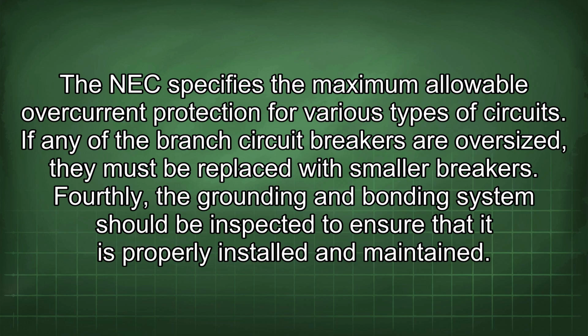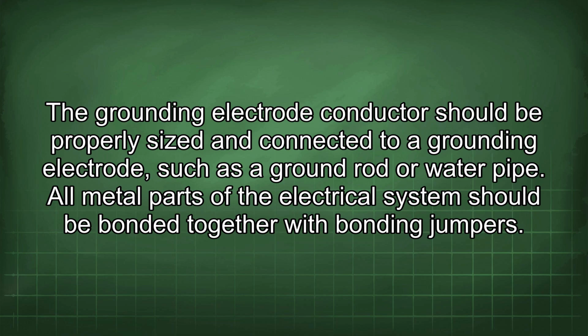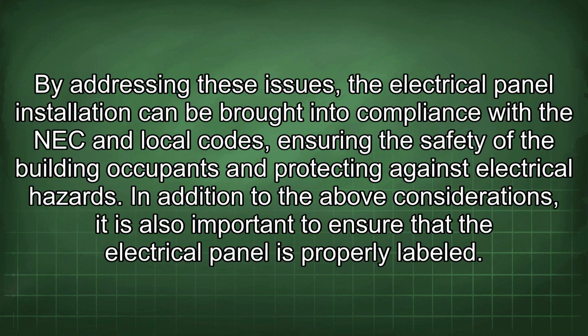Fourthly, the grounding and bonding system should be inspected to ensure that it is properly installed and maintained. The grounding electrode conductor should be properly sized and connected to a grounding electrode, such as a ground rod or water pipe. All metal parts of the electrical system should be bonded together with bonding jumpers. By addressing these issues, the electrical panel installation can be brought into compliance with the NEC and local codes, ensuring the safety of the building occupants and protecting against electrical hazards.